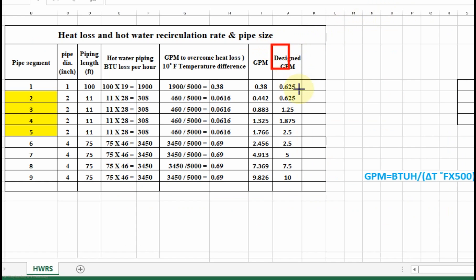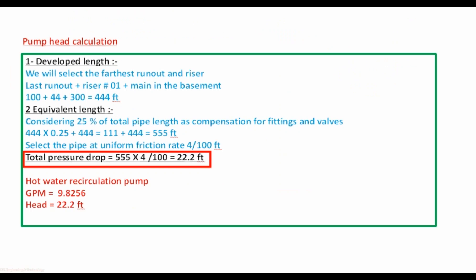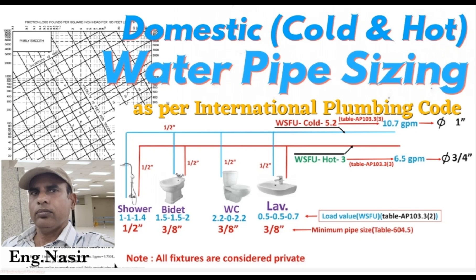We have calculated the GPM for each pipe segment. Now you can select the pipe size for the hot water recirculation piping network using the International Plumbing Code. After designing the pipe sizes, you can calculate the actual pressure drop in the piping and accordingly select the head for the hot water recirculation pump. For designing hot water recirculation piping, you can watch our video on domestic cold and hot water pipe sizing — the link will be in the description. Thank you very much.